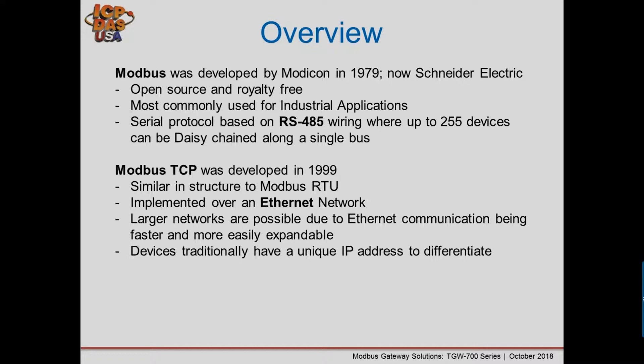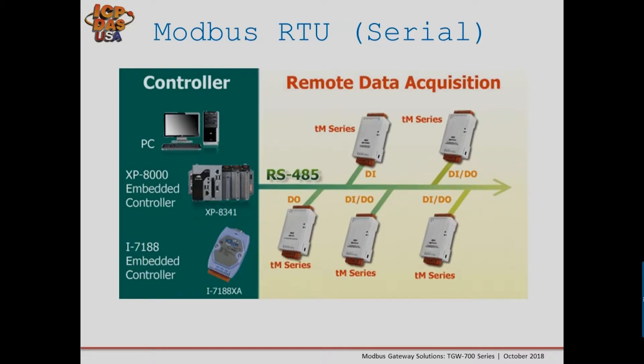The main difference between Modbus RTU and Modbus TCP is that Modbus TCP is implemented over Ethernet. It can be added to an existing network infrastructure and is similar to Modbus RTU in master-slave configuration. Larger networks are possible due to Ethernet being faster and more expandable. Devices use unique IP addresses rather than individual Modbus slave IDs.